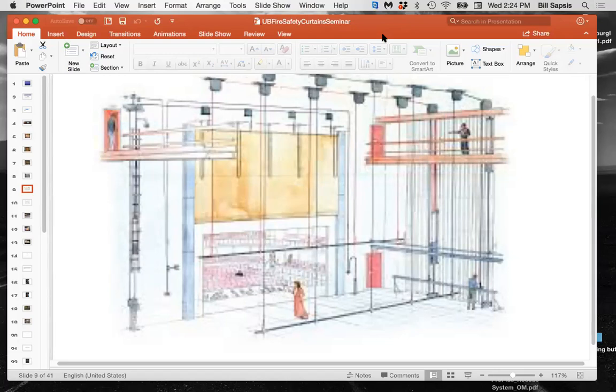Fire curtain came down, the smoke doors opened up, but somebody had taken one of those portable classroom flagpoles, 8 foot tall with an eagle on the top of it, kind of a thing. And they stuck it in the smoke pocket. And the smoke pocket on the screen here is this grayish device here and over here on the other side. And it is the track that the fire curtain runs in. And they stuck that right in there.